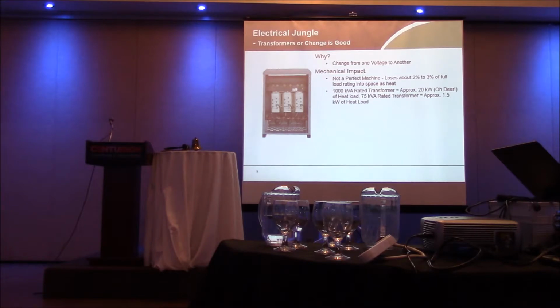So we try to use a higher voltage all the time to avoid having too many transformers. If I get a big load, I want to use a high voltage, I avoid a level of transformation, and I avoid having to get the heat out. How do we remove heat from my electrical room, typically? Exhaust fans. And what do exhaust fans need? More power. So I have to spend energy to get rid of wasted heat energy.